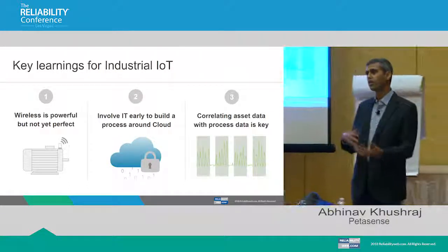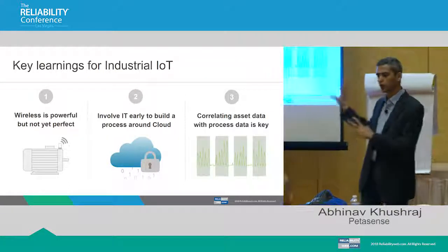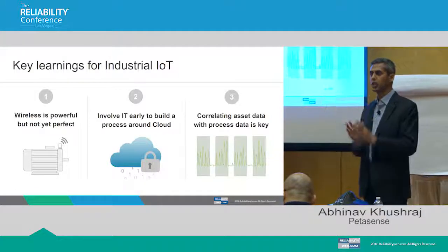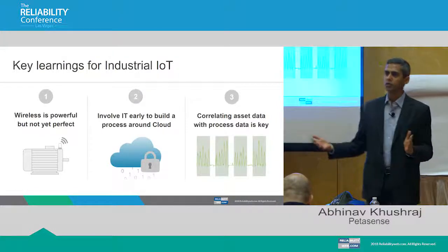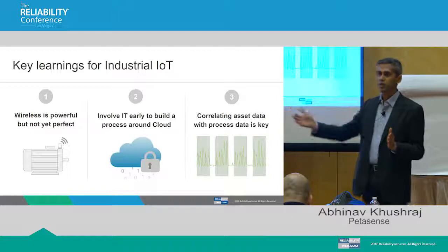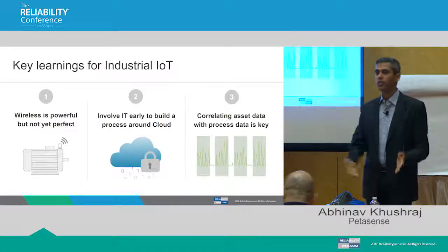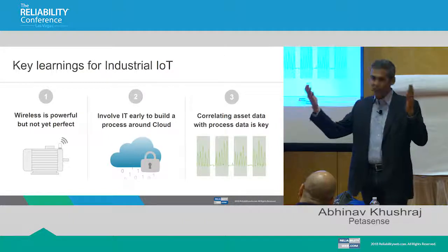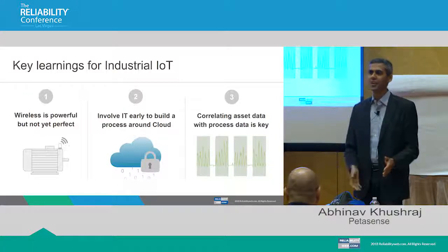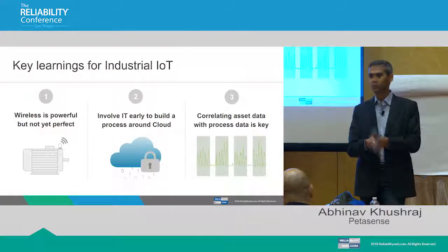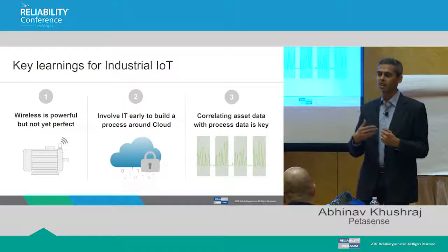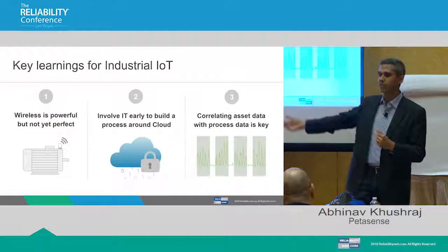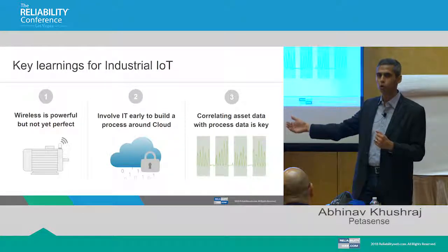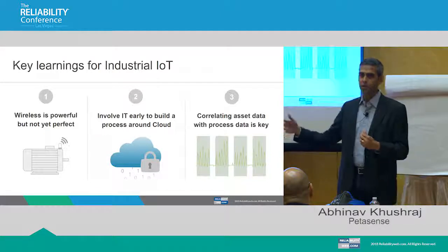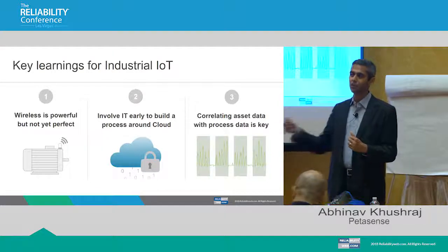But multi-parameter, I want to add one point on that. What we got from that, we took into our next product, which we're about to launch. I won't talk about the product, but the concept: when you look at a rotating machine, load is important, running speed is important. If you just look at the overalls, you're going to get garbage. If you just look at the same 1x in your spectrum, you'll get garbage. You need to look at it in comparison with your other parameters, what's your load, what's your running speed, so you need other sensor inputs coming in.